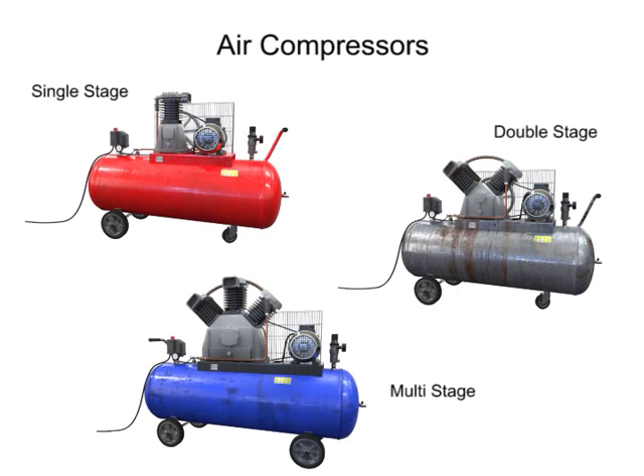If pressures of more than about 175 psi are needed, multi-stage compressors should be used. On these larger compressors, cooling may take place by circulating water instead of air. To reach a pressure of 2500 psi, as many as 6 or 7 stages may be needed with cooling between each stage. Their versatility makes compressors one of the primary components in air production.